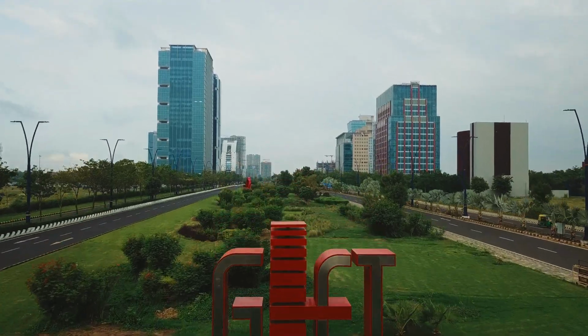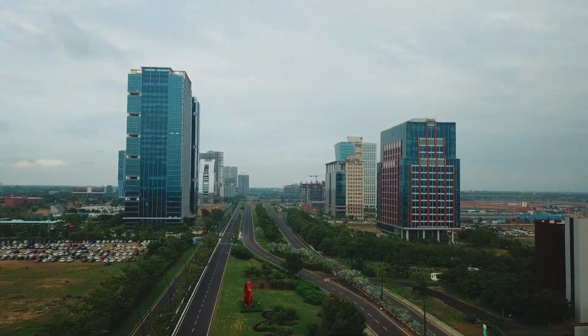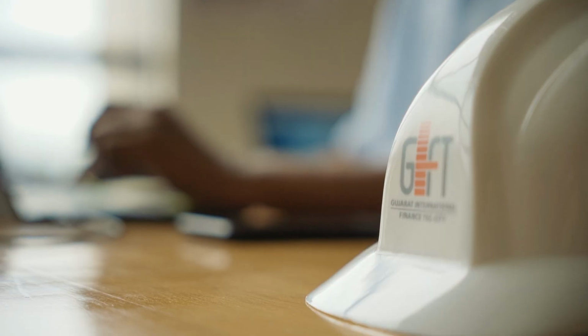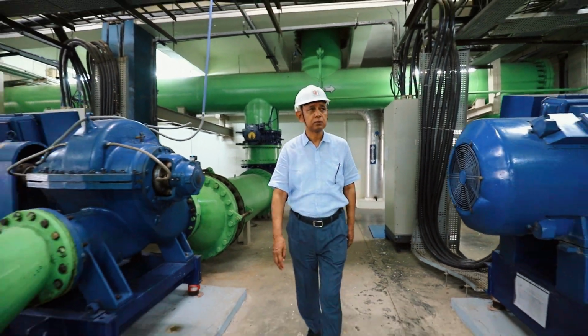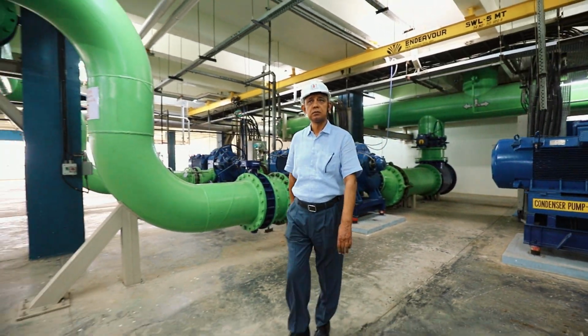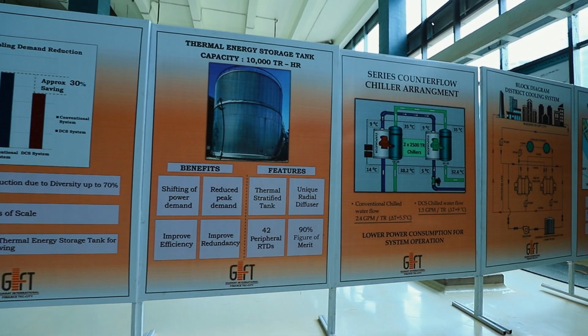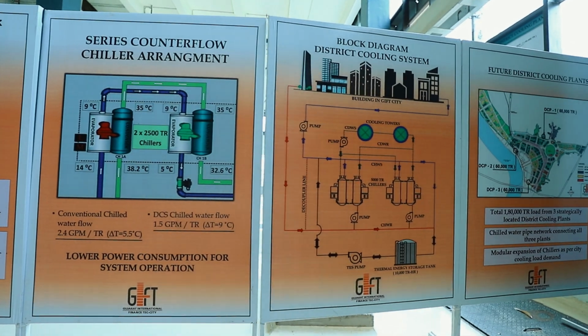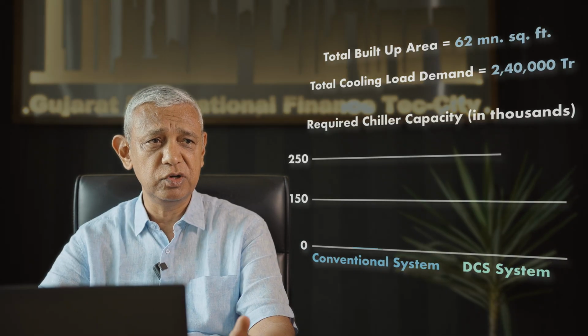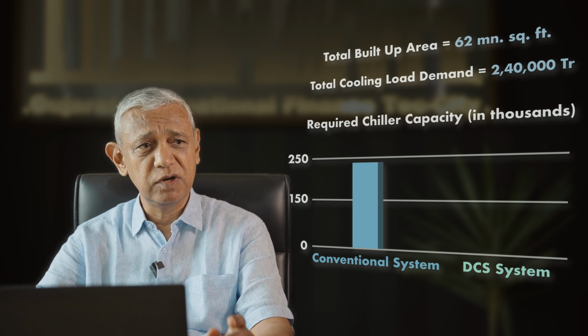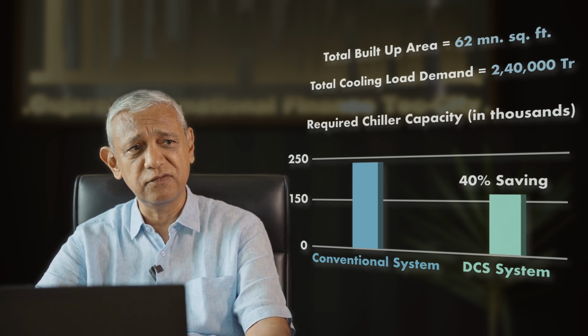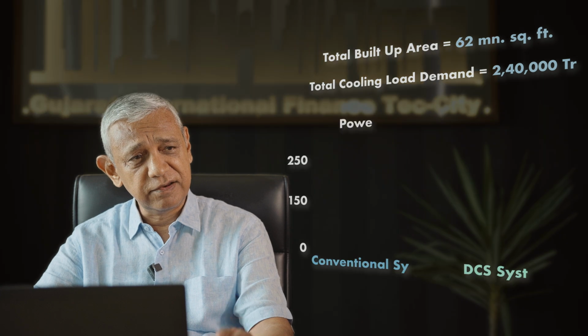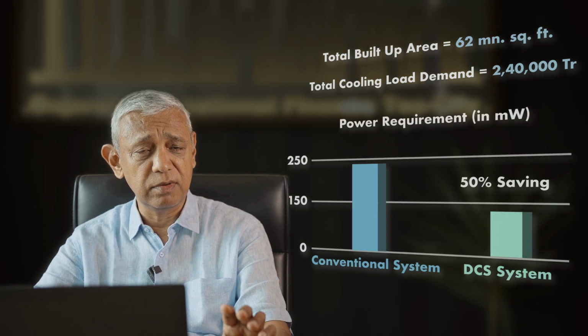GIFT City has successfully showcased that district cooling can be easily implemented in greenfield projects. At such a large area of over 800 acres, it may not be feasible to use any other method except district cooling for air conditioning the entire city. Conventionally it would have required 240,000 tons of air conditioning, but with district cooling we only need around 170,000 tons, a remarkable saving on capex. The electrical demand also comes down substantially, by around 50%.